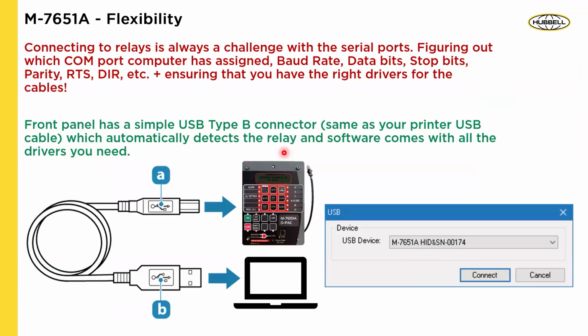The other challenge we see is number one, when you try to connect to the relay, how do you connect it? Well, I gotta have a specialized cable. I gotta have the right drivers. If I'm connecting through serial, I need to know which COM port it's going to be on my computer, right? What's the baud rate? What's the data bit, stop bits, parity, RTS? So blah, blah, blah, right? So it's a lot of this information that you have to figure out before you even step your foot in the relay, so to speak.